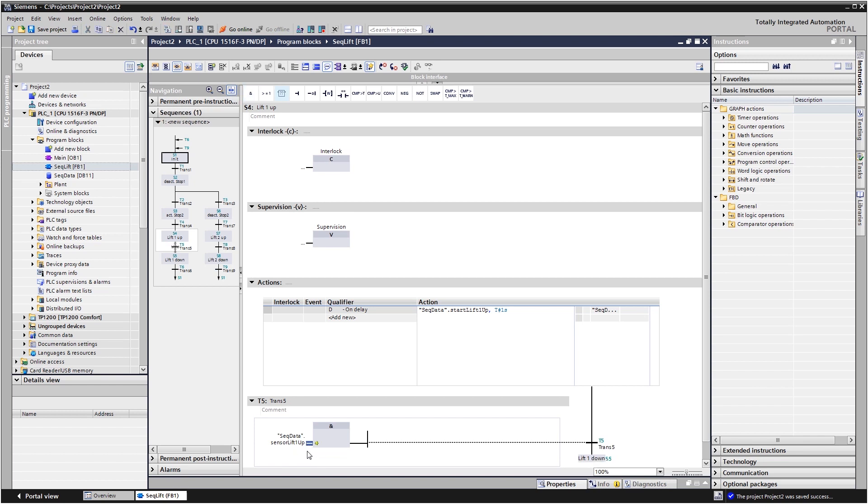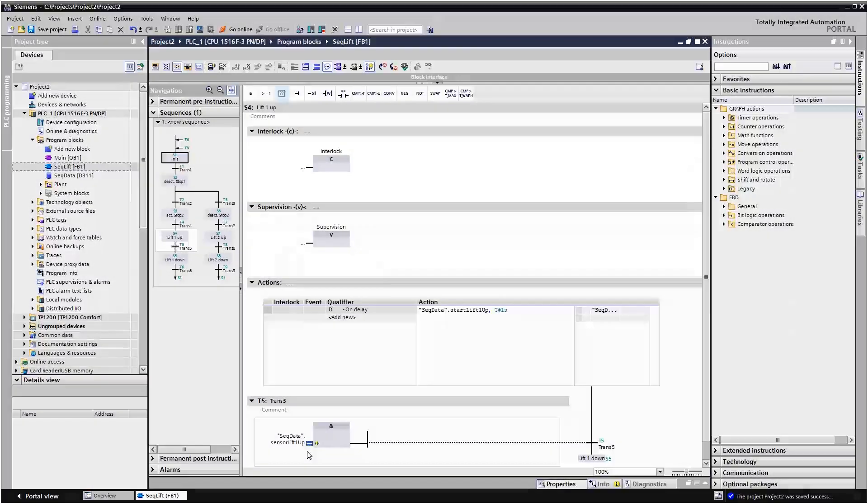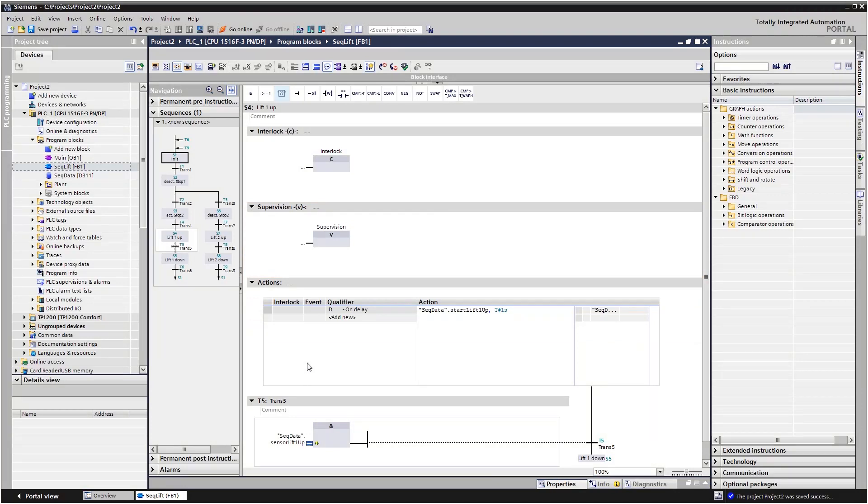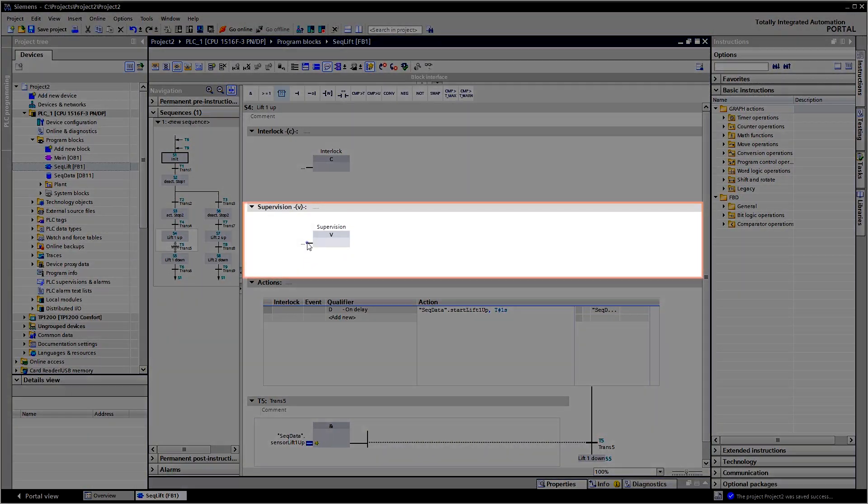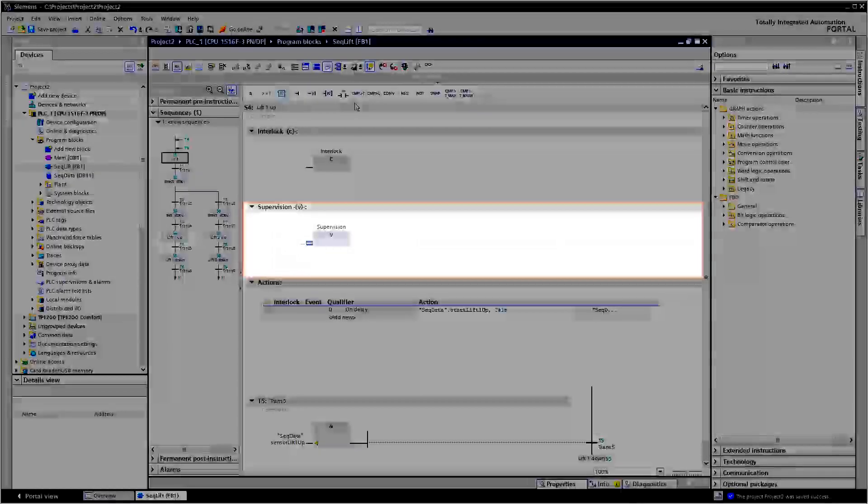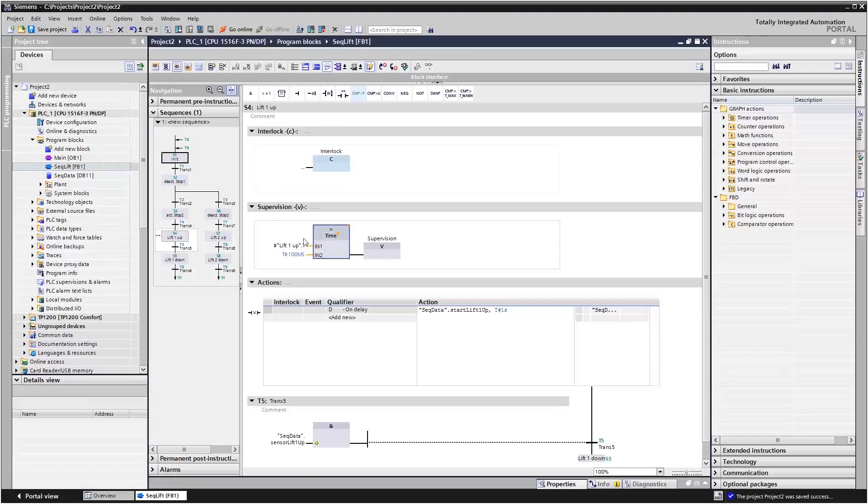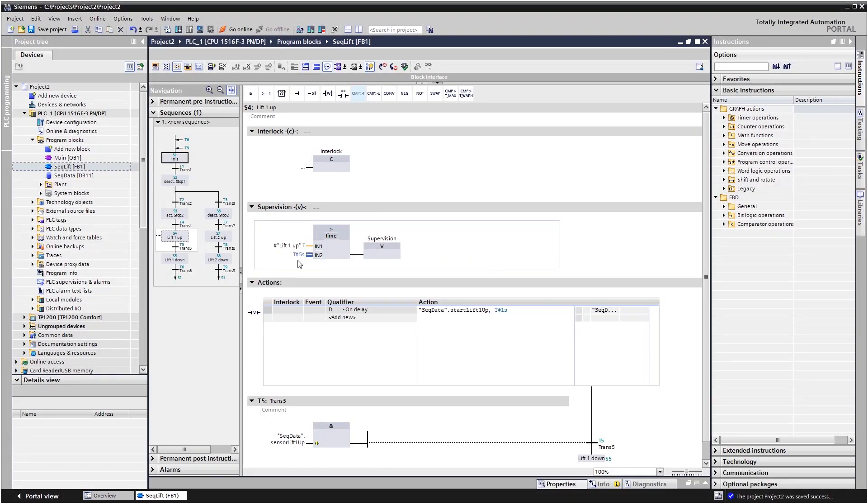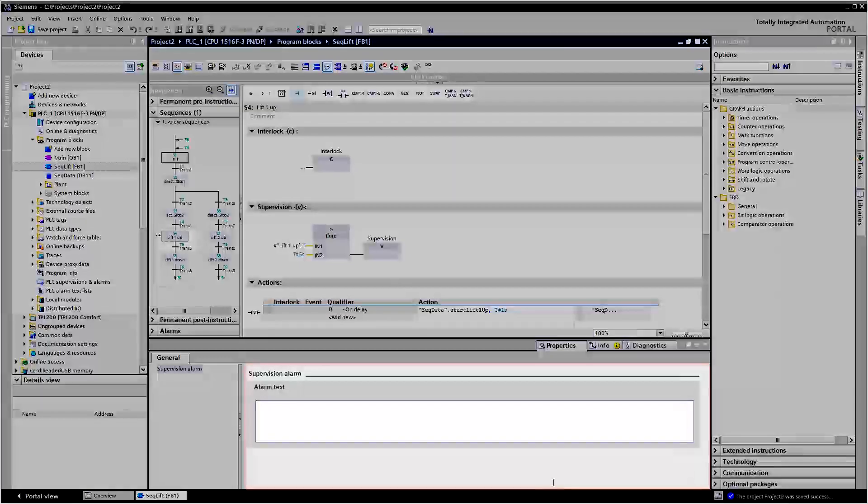You can uncover faults via interlocks and supervisions. Under supervisions, you observe the step duration, for example. The corresponding alarm text is already integrated into GRAPH and does not need to be programmed.